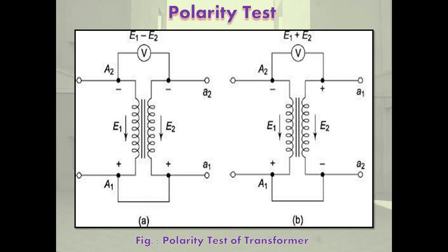If X and Y, or A1 and A2, are connected together, the voltage across is found to be, for example, 230 minus 30 equal to 200 volt, and the polarity is said to be subtractive. If, on the other hand, the terminal connections are such that the voltage across A2 and A1 is 260 volt, the polarity of the terminals is additive, as the voltages 230 and 30 now get added, corresponding to the series connections.